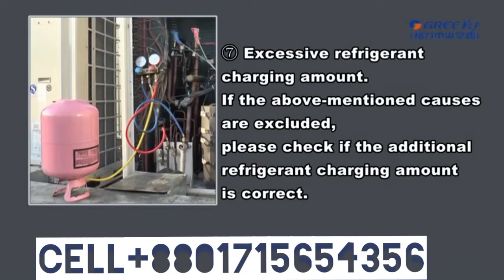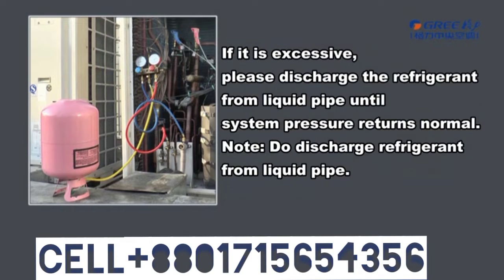7. Excessive refrigerant charging amount. If the above-mentioned causes are excluded, please check if the additional refrigerant charging amount is correct. If it is excessive, please discharge the refrigerant from the liquid pipe until system pressure returns to normal. Note: do discharge refrigerant from the liquid pipe.